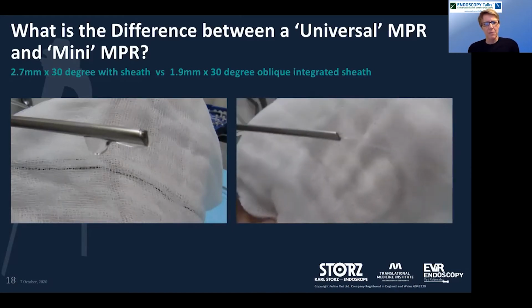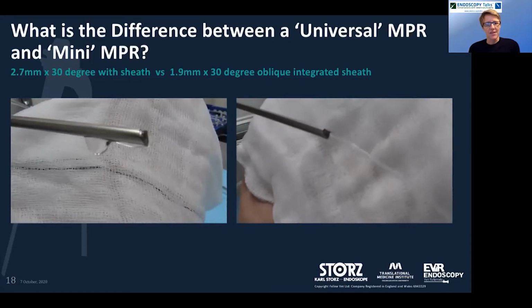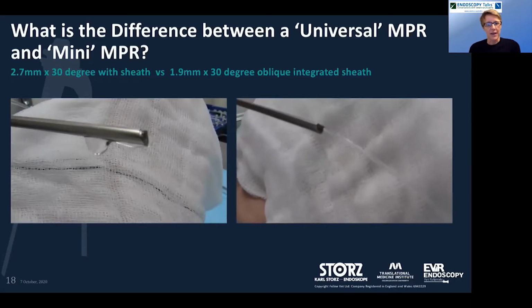So with the mini MPR, as you can see, it's all integrated, and the irrigation goes over the top of the endoscope itself rather than around it. And so it gives a really nice forceful jet. That's gravity fed irrigation. So that coupled with a 10 or 20 mil syringe on the egress port will give that extra additional jet of flushing if you need to remove any debris. So this is a really nice endoscope to use.